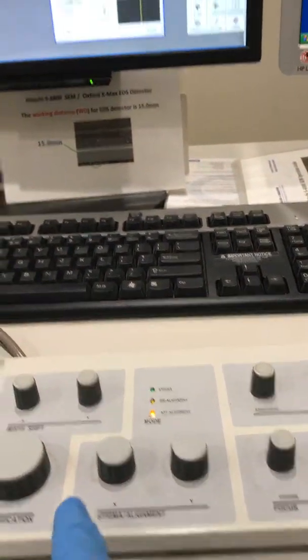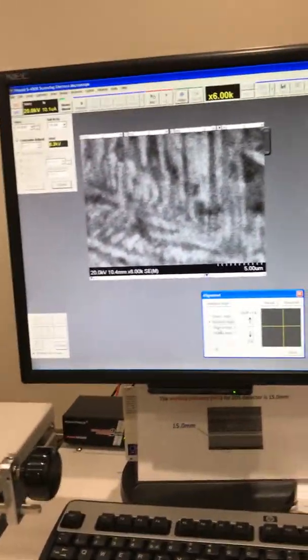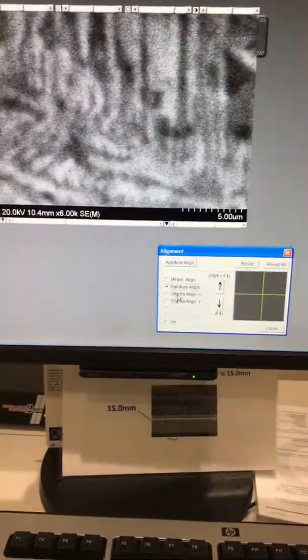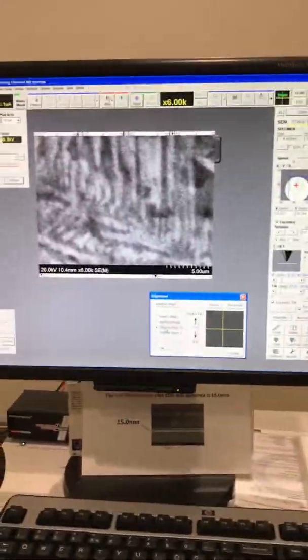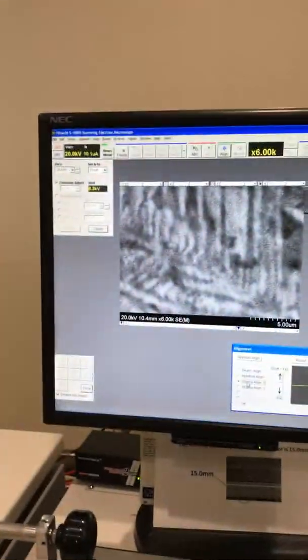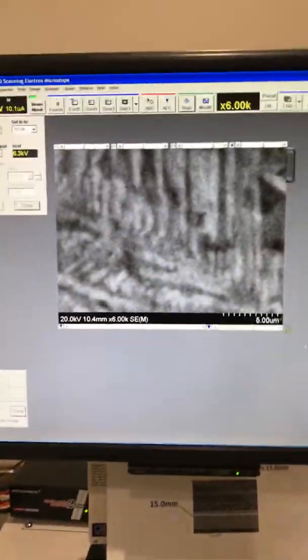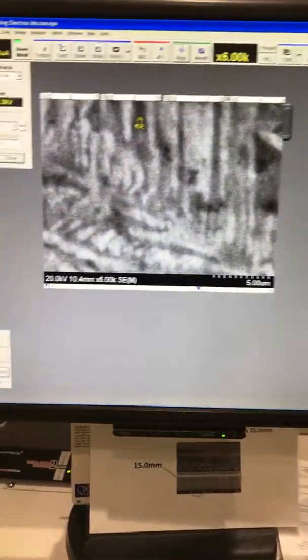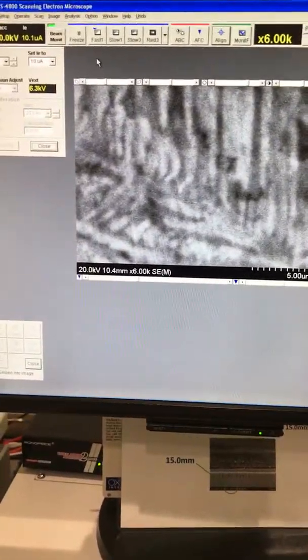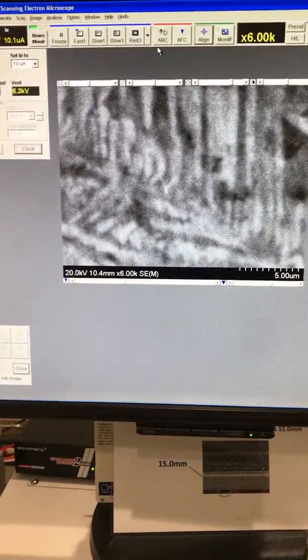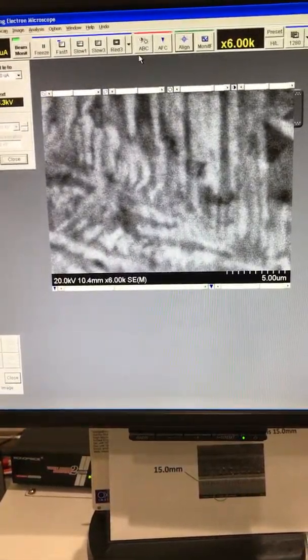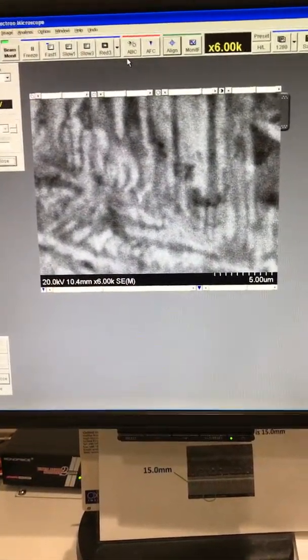I can increase my magnification and check for higher magnification to see if I can do a better alignment. Next is the stigma — make sure there is no X and Y movement, so adjust the stigmatics the same way. Then close your window. That's the alignment of this microscope. Next, I'll show you how to adjust your astigmatism manually in the next video.